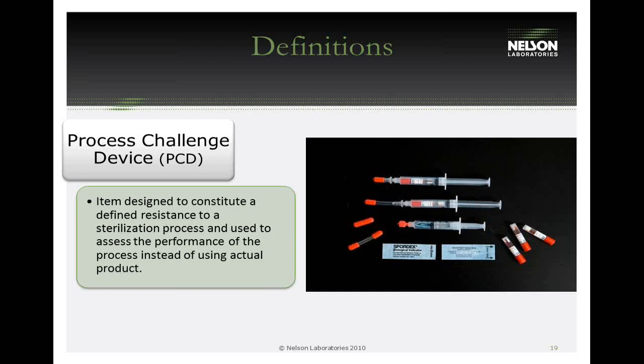Spore-forming organisms cannot be effectively used as BIs for radiation sterilization, because the most radiation-resistant organisms are those that repair their DNA most quickly — typically not spore formers, but organisms like Micrococcus. Additionally, about 30% of North American organisms are equally or more resistant to radiation than Bacillus pumilus, the commonly marketed radiation BI. For that reason, radiation sterilization relies on dosimetric release based on actual product bioburden rather than biological indicators.